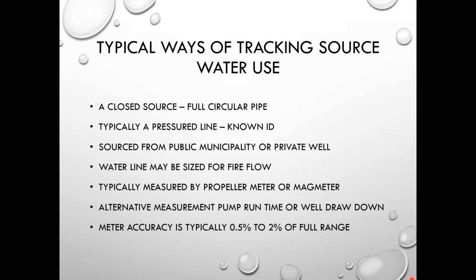Typically, what they measure with in a full pipe is a propeller meter or a mag meter. Alternative measurements for your source water would be measuring pump run times on your pumps. So you're just taking your head versus flow, your pump chart, and knowing what the typical run pump is. If it's a 50 gallons a minute pump, you multiply it by the time, and you can figure out a rough idea of your volume. And then also doing well draw downs.